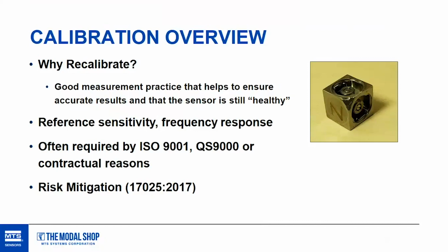But oftentimes, even things like scratches, gouges, dents, or even internal damage that you just can't see happens to accelerometers throughout their lifetime. It depends on how they're handled and how they're used.